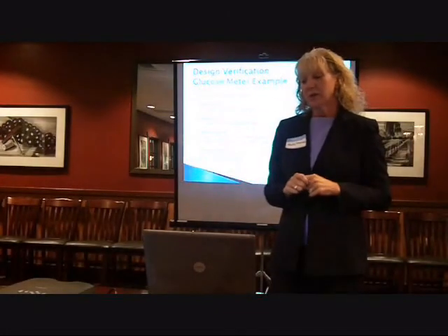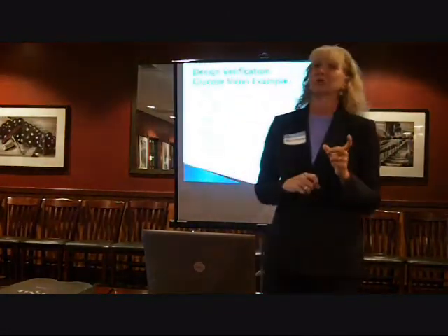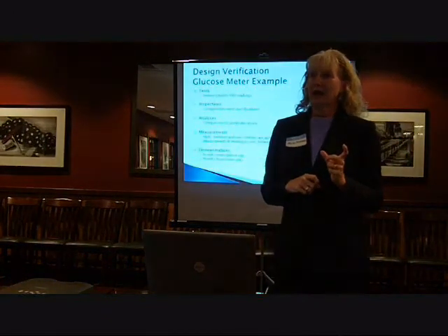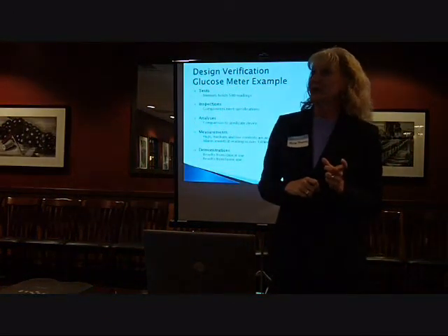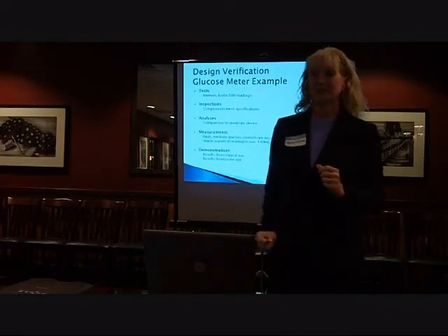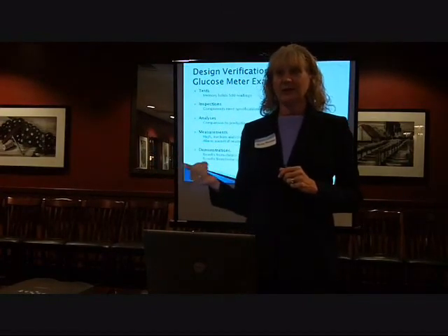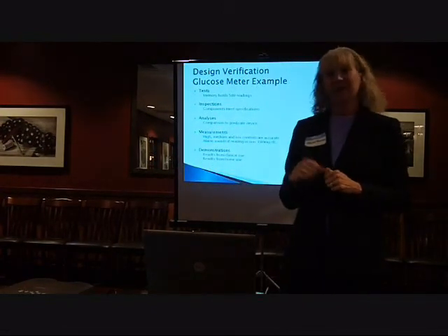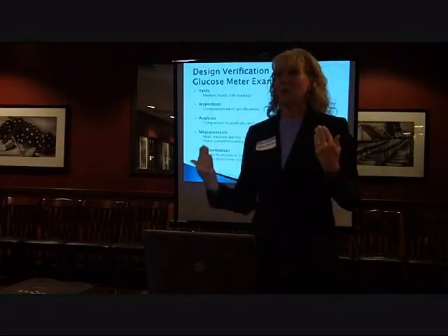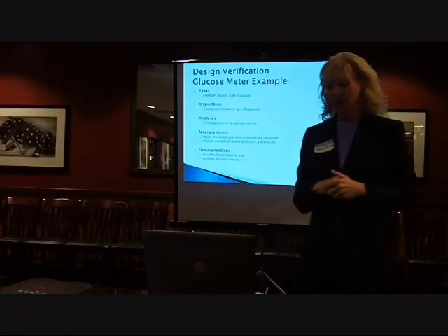This is where you might do a comparison to the predicate device. So you may have a new and improved glucose meter, and in order to get that cleared through the FDA, you're going to have to say it works as well as this other one that's out there. So you might look at the data for that predicate device and verify that you are matching up with whatever its outputs are, matching up to those results.